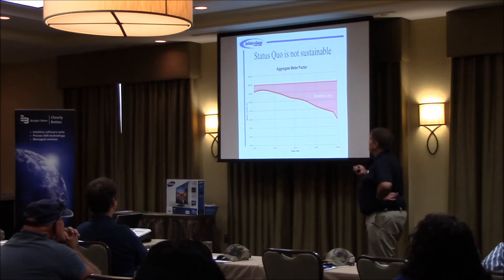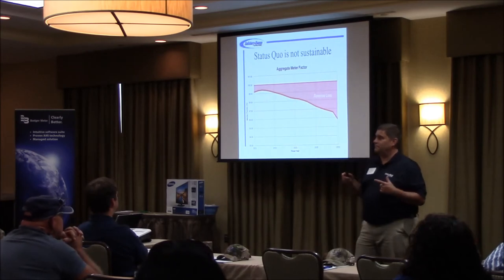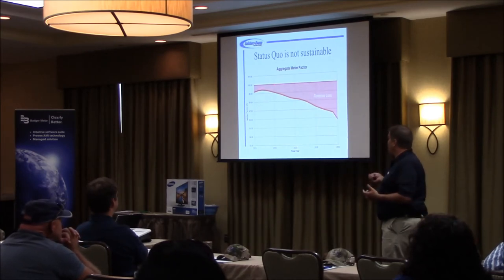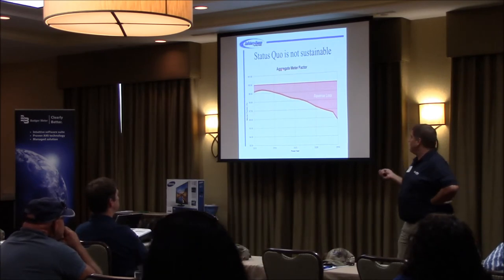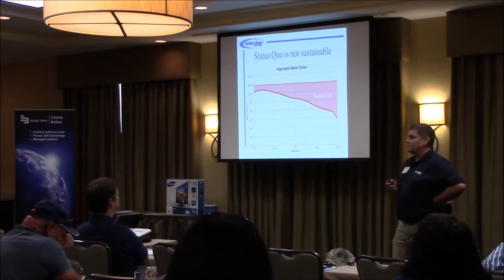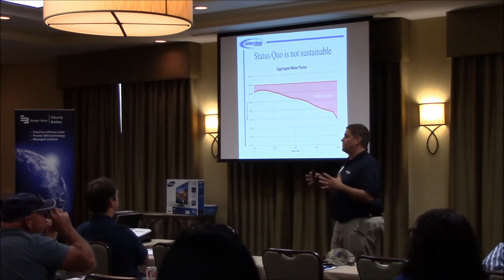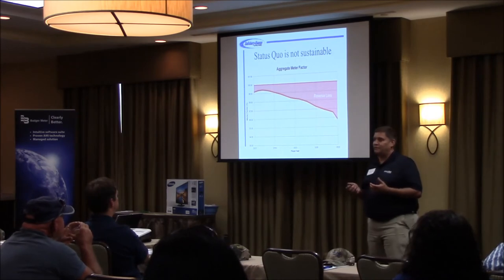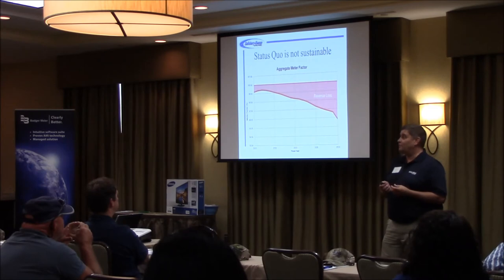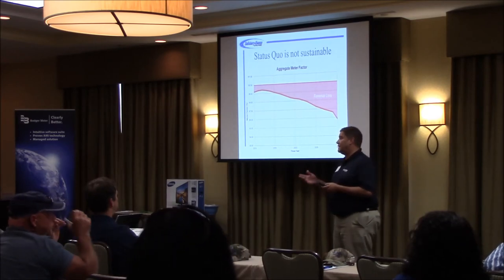And so then we got looking at, okay, we still have to change those meters out through our regular program. And as we change those meters that are over-registering out, our revenue gap gets bigger and bigger. So that's where we were looking at, okay, what do we do? Through this, with a mechanical meter, we came to the conclusion, I think just about everybody else has, that at about 14 years, the revenue loss from those mechanical meters becomes unsustainable, where you're losing more than it costs to replace that meter.